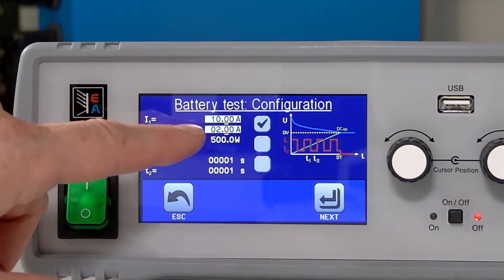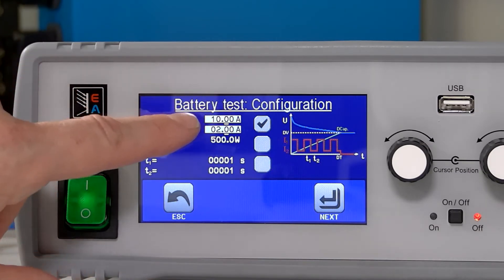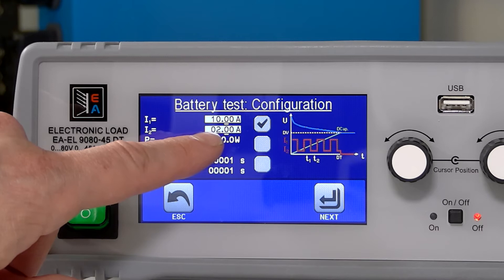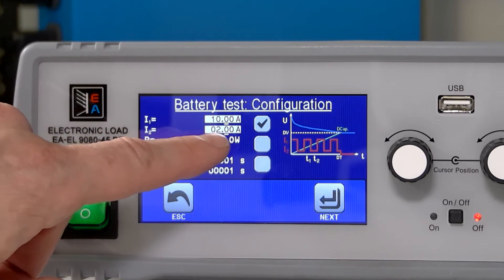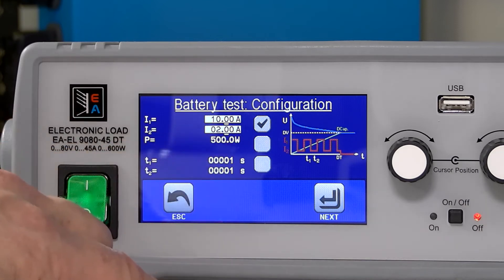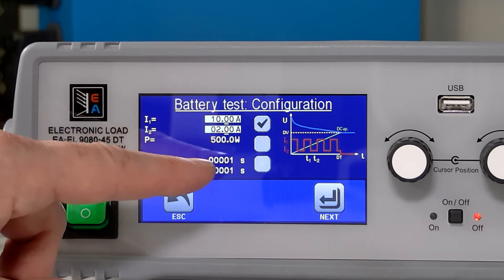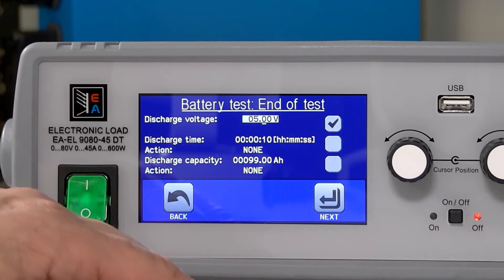The test configuration gives you a little display so you know what variables you're programming and what those mean. We're going to start off discharging the battery between 10 amps and 2 amps — those will be the two power levels we're going to discharge at. We're going to do that not exceeding 500 watts, and the times for each of these two discharge levels are going to be one second. So it's basically just going to alternate between those two levels until we hit the end of the test.